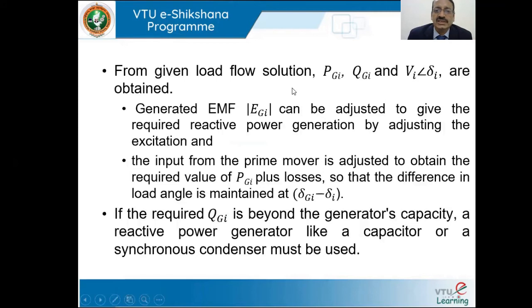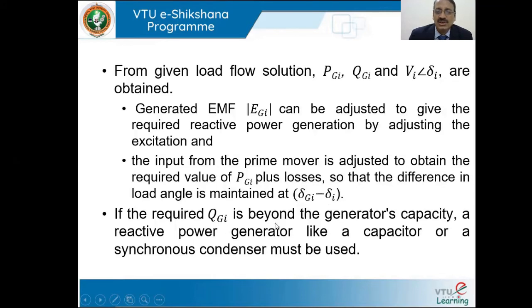From a given load flow solution, PGi, QGi, and Vi at angle delta_i are obtained. The generated EMF EGi can then be adjusted to give the required reactive power generation by controlling the excitation. The prime mover input is adjusted to obtain the required PGi plus losses, maintaining the load angle delta_Gi minus delta_i. If the required QGi is beyond the generator's capacity, an additional reactive power source such as a capacitor or synchronous condenser must be connected to the ith bus.